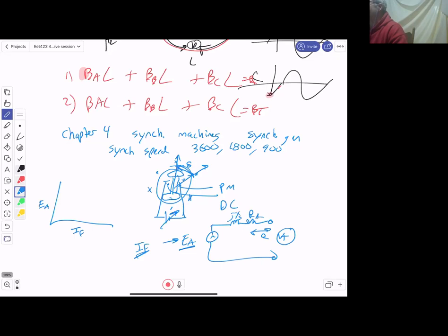And that was exactly the opposite back in the day. The plant that I'm the most familiar with is Northfield Mountain, which I think is the second largest generating station in New England. There's 1,200 megawatts capability there. They were built in the 60s because there were some nuclear plants coming online, and nuclear plants run really well baseload. They don't like to go up or down.